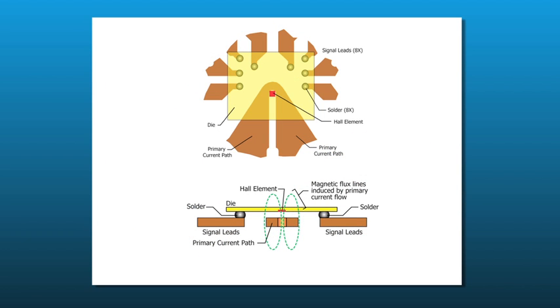The sensor works by placing a Hall plate magnetic sensor above the loop of an integrated primary current path. The field from the current being measured is strongest above this loop and proportional to the current.